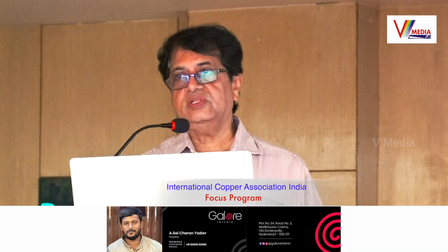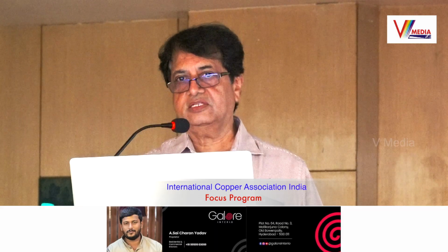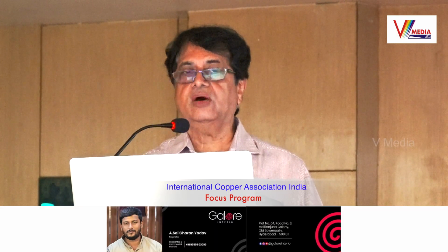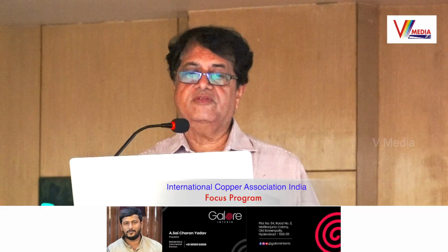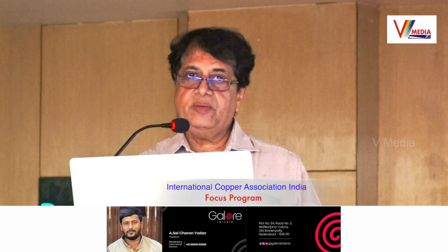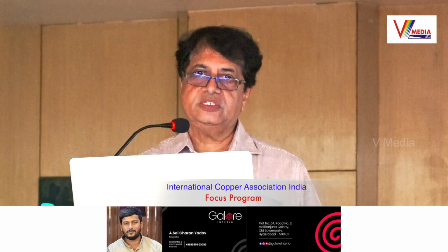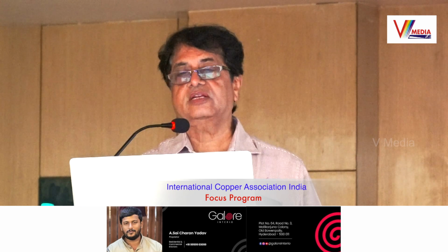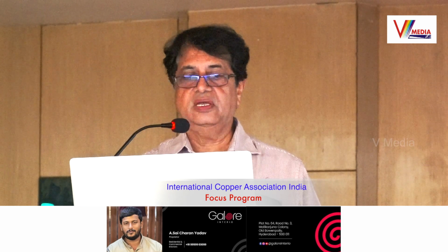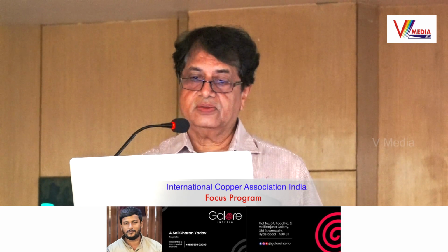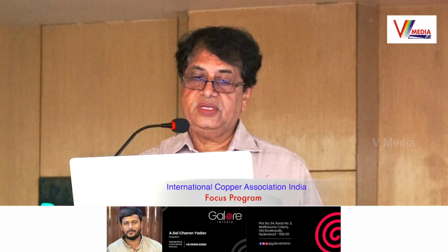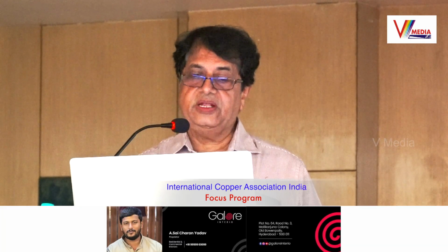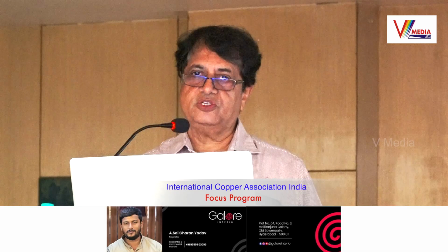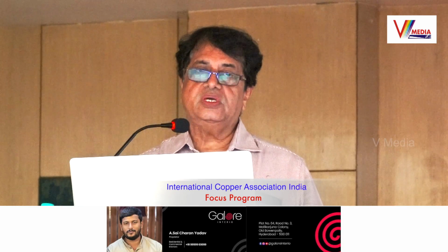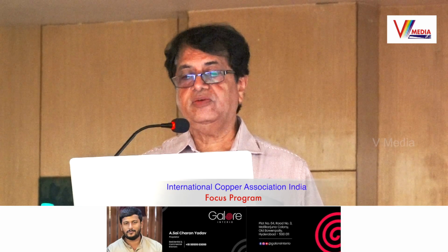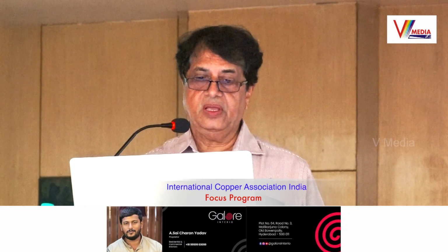The shaft assigned for the electrical cable shall not be used for any other services like your pumping lines or downcomers of the fire system or any LV system. LV system may be allowed within the electrical shaft, but there should be segregation between the electrical cables and the LV system lines. So these are the requirements given in the code. So shafts should be designed in accordance with that. This independent shaft should, as far as possible, be nearer to the energy meters which will be installed later on in the building.